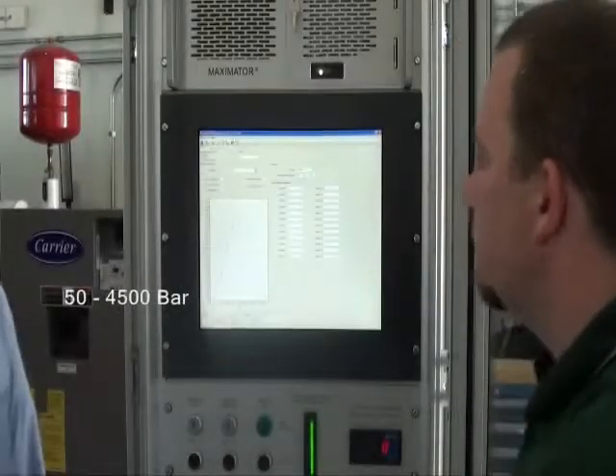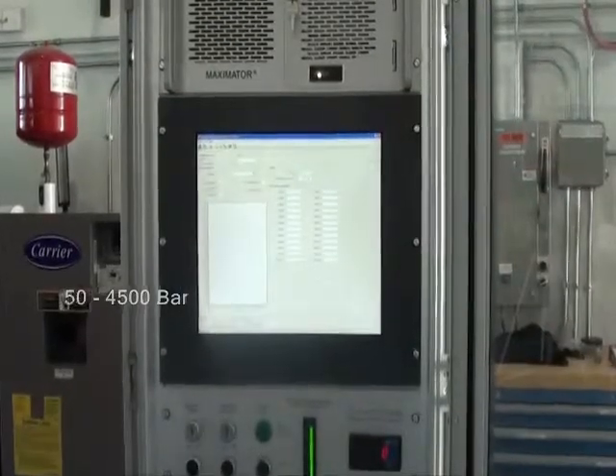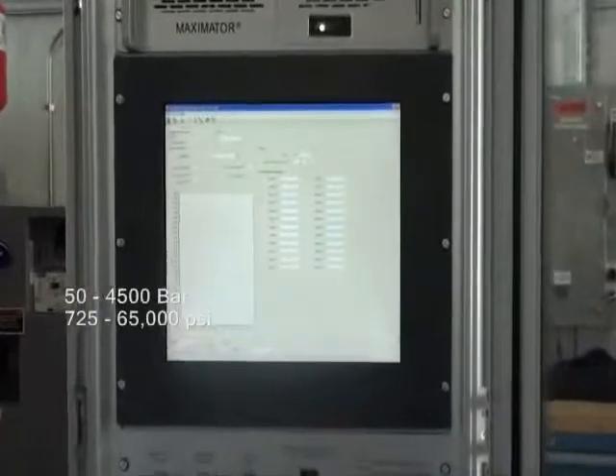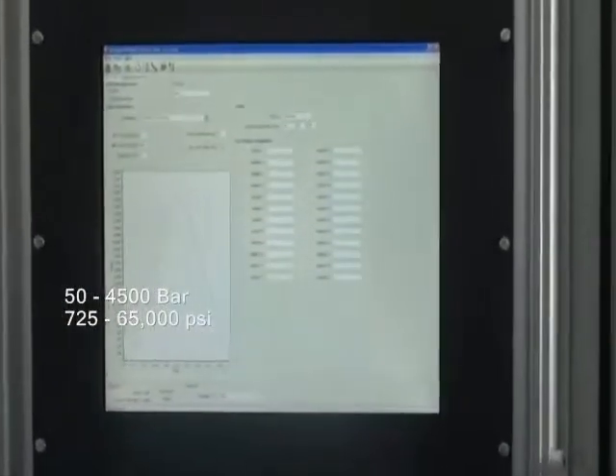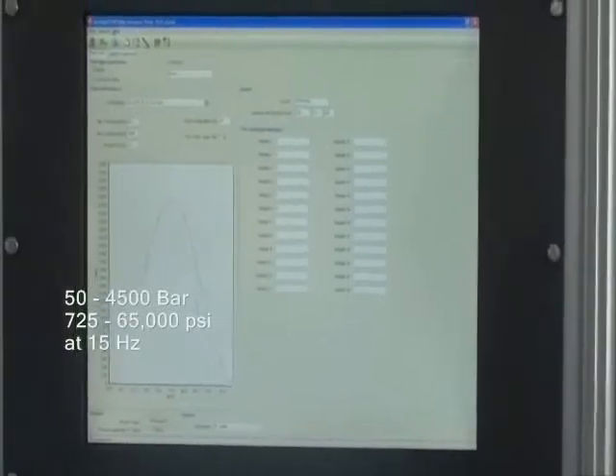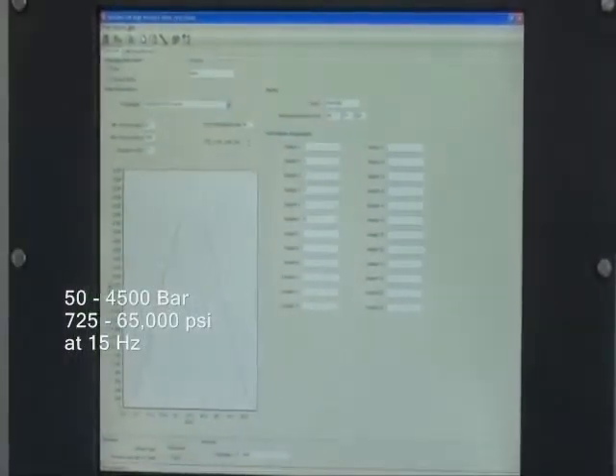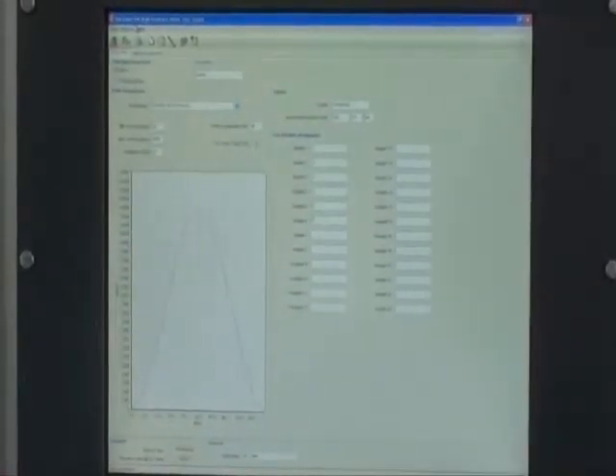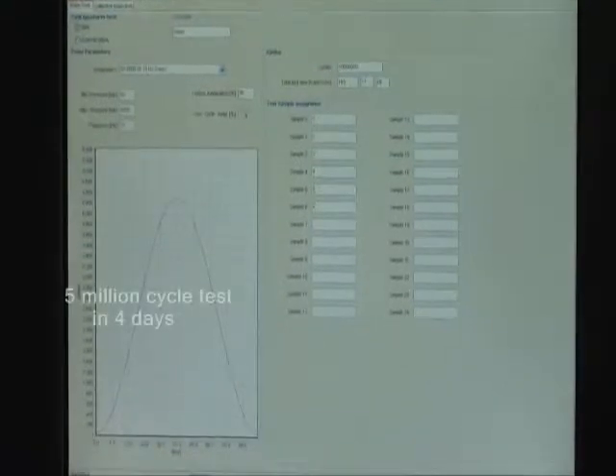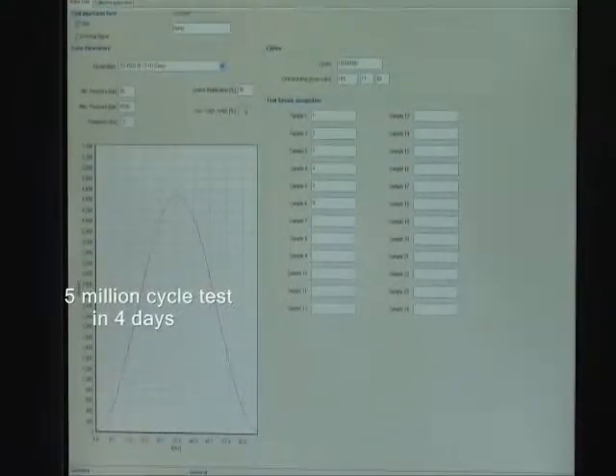Alright, the test parameters for our demonstration today will be a test from 50 bar to 4,500 bar. It's about 725 psi to about 65,000 psi. We'll do that at a frequency of 15 hertz or 15 cycles per second. This is the kind of typical test we run for a customer that's trying to validate a new design or even a material change on an existing design. We can run a 5 million cycle test in roughly 4 days with this.